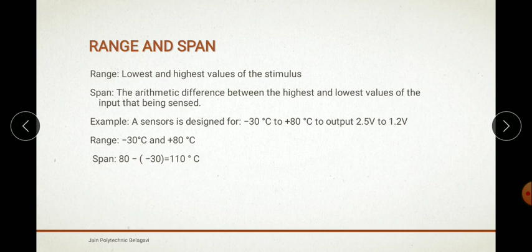The example for the sensor is, consider a thermometer, a temperature sensor, used to sense temperatures from minus 30 degrees to plus 80 degrees with the output value of 2.5 volt to 1.2 volt. Here the range is defined as minus 30 to plus 80, that is minus 30 degrees to plus 80 degrees. Next one is the span. The span is nothing but the difference, that is 80 plus 30, that is 110 degrees, the difference between the highest value and the lowest value. Next, the error and the accuracy.